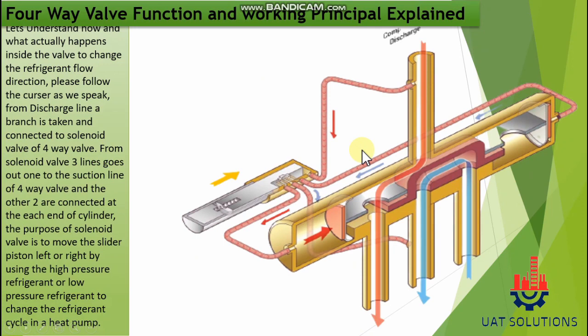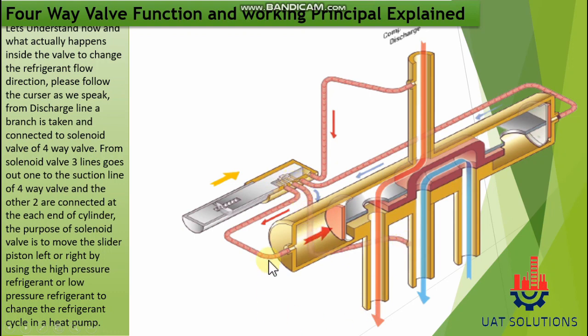Let's understand how and what actually happens inside the valve to change the refrigerant flow direction — please follow the cursor as we speak. From the discharge line, a branch is taken and connected to the solenoid valve of the four-way valve. From the solenoid valve, three lines go out: one to the suction line of the four-way valve, and the other two are connected at each end of the cylinder.